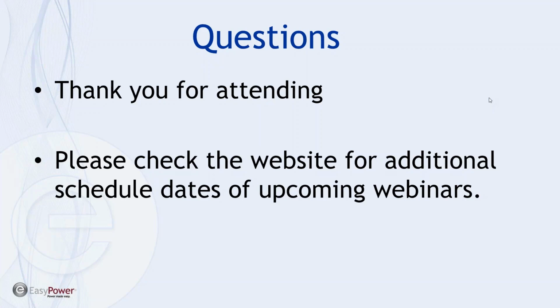That's a simple answer. Now, I know many audience members, especially experienced ones, will say no, that's not the case, because during the fault the impedance will change, or the fault current amount will change. The IEEE working group, and also a lot of NERC fault current study working groups, have come up with a new model last year and this year, called a voltage controlled current source, where the fault current from the PV or wind turbines is based on the terminal voltage. That means it takes an iterative approach: initially I use my Thevenin equivalent impedance to get my fault current, then I back calculate my terminal voltage, redetermine my new fault current based on this voltage, recalculate my Thevenin impedance, and recalculate the fault until it converges.